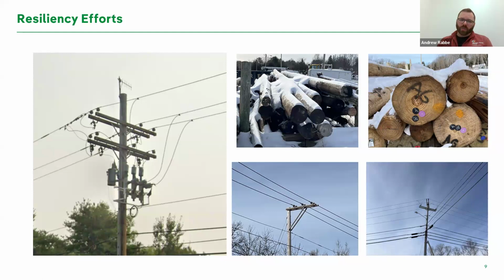So what this does is, right now your station circuit breaker will go 3 shots to lockout, they call it. If it senses a fault, it's going to open quickly, and then it's going to try and close back in, hoping that whatever it is, if it's a small tree branch, that close back in will either burn it off or it'll pop off the line. Because what you're doing is you're exciting a ton of electrons in the line when you're doing that. It'll do that 3 times. If it can't clear it, then it opens up and goes to what's called lockout.